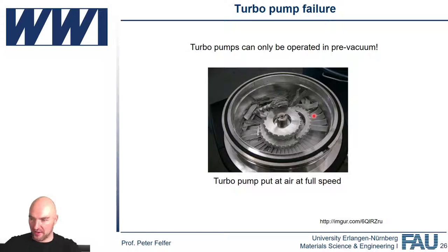The only problem with turbo pumps is they're spinning extremely fast, so they are very susceptible to mechanical damage. For example, in Japan, where you have a lot of earthquakes, turbo pumps don't like earthquakes. The other thing is, if you have an inrush of air, same story: a lot of mechanical force into your pump, and you might just break it. We haven't broken a turbo pump on an atom probe yet, but we have broken turbo pumps on electron microscopes, for example, where there was a problem with the software. Turbo pumps can be broken, and the bits and pieces can fly around and damage a lot of stuff.